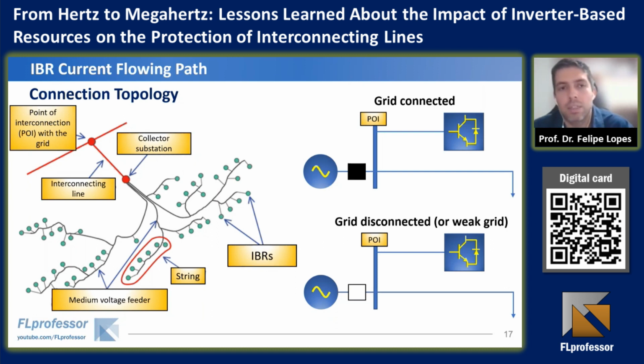But at that moment, when everyone was concerned about the problem that IBRs could pose on protection schemes, it was very enlightening for me. And basically, this is a traditional topology of connection. Here we have IBRs. They can be wind turbines or photovoltaic panels. Here the strings. There is a medium voltage feeder connecting these IBRs to a collector substation. Then there is an interconnecting line, which is the main subject of our studies, and then the point of interconnection. Some people say that this point of interconnection is here together with the collector substation, but just for the sake of simplicity, I am considering that the point of interconnection is here.